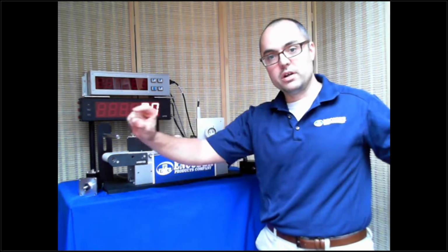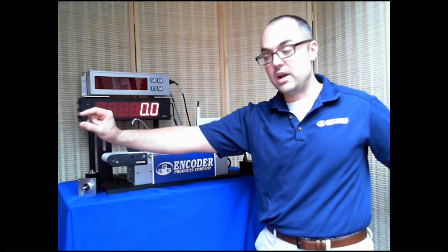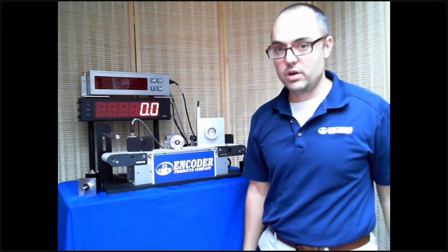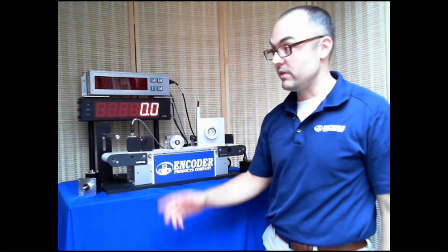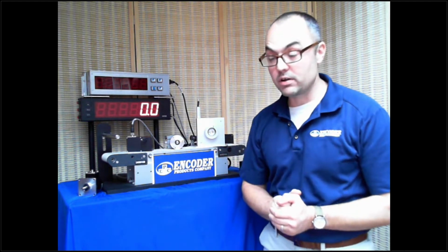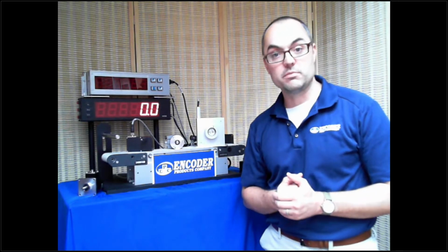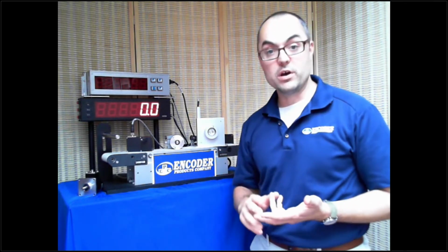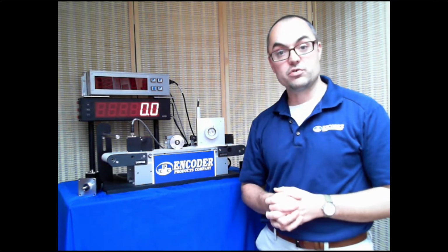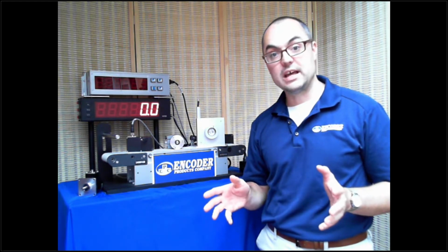They're little pieces of either metal or maybe gold foil or plastic that you would put on your entire distance of linear travel. The trouble with scales is, what if you have 20 feet or 40 feet you've got to move? I just did a 20-meter gantry crane. That would be a really long scale. It would be expensive and they're prone to failure if you have contamination. Maybe you have oil and coolants, maybe you have metal chips. If you scratch or damage those scales, you now lose positioning in that area.